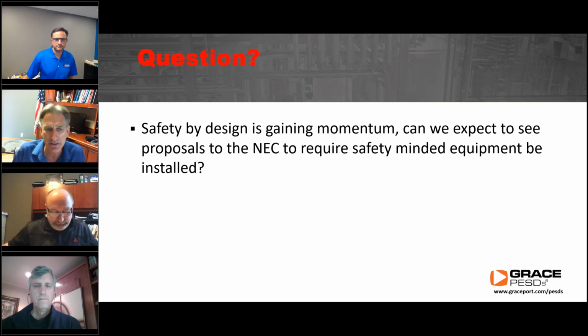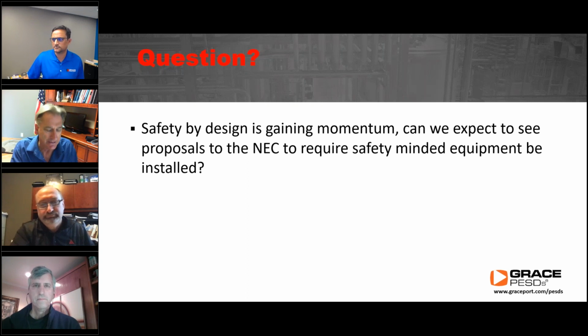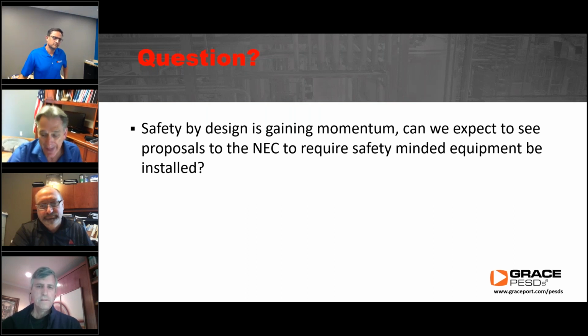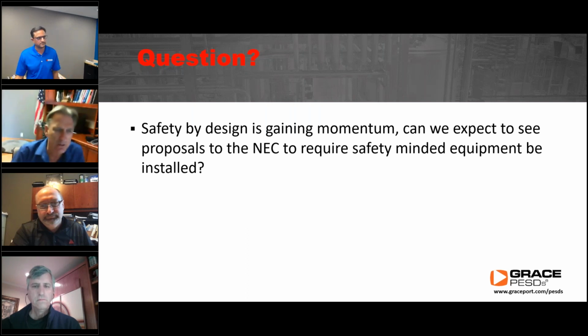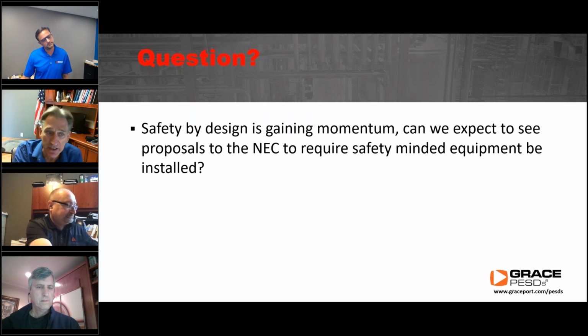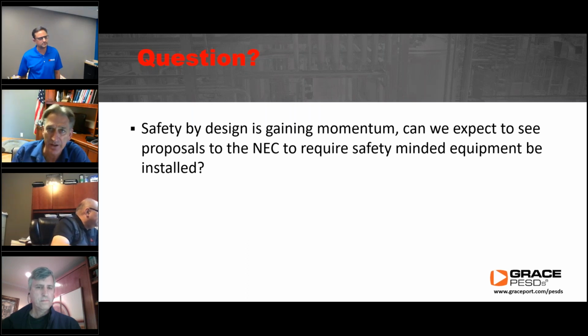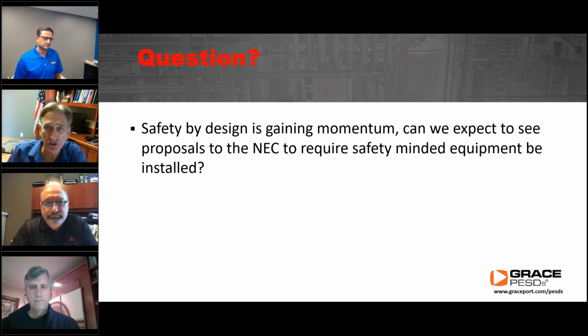But I thought about a few things that are in the NEC. A big one that's been in there for a while is just arc flash warning in 110.16 in the National Electrical Code. And then in the 2017 edition, they added an A and B. It used to just have a very general statement, and then section B was added in the 2017 edition. Now, the newest edition we have out there, the 2020 code just came out about a month ago. But very little of this changed in the 2020 edition.